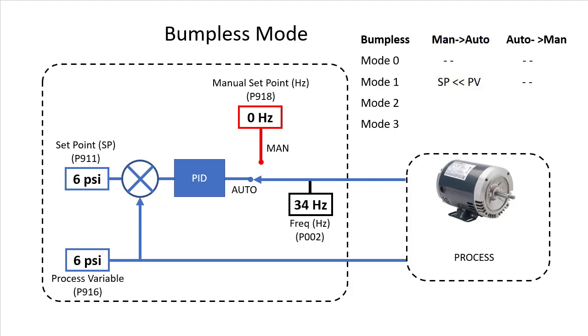The CFW series of drives also lets you control the transfer when exiting PID. Similar thing, suppose PID is reliably holding the process at some level and when you switch to manual mode you don't want any sudden changes in the motor speed.